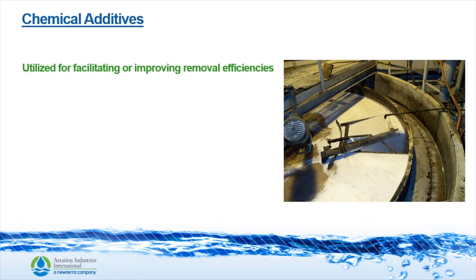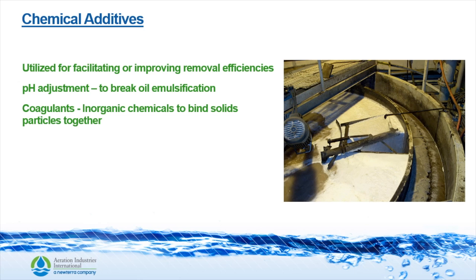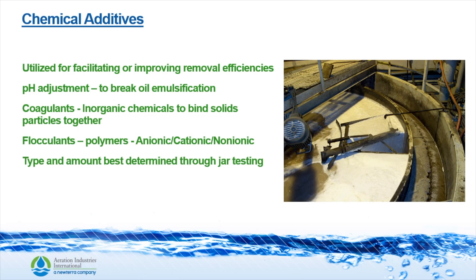Now I would like to touch on why you might add chemicals to the system. By adding chemicals, you can increase flocculation and improve your removal efficiencies. You can use chemicals to adjust the pH so you can break the oil emulsification. Coagulants are used to bind particles together, and flocculants like polymers are used in the settling process. The best way to determine what chemicals are best for your system is to do jar testing.